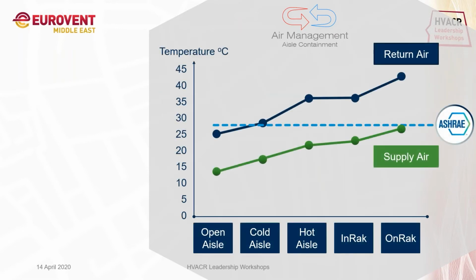Looking at aisle containment air management against the related temperatures, as you can see in the open aisle, the first one, the return air temperature is about 24 to 25 degrees Celsius, whereas the supply air will always be in a range of 12 to 13 degrees Celsius.